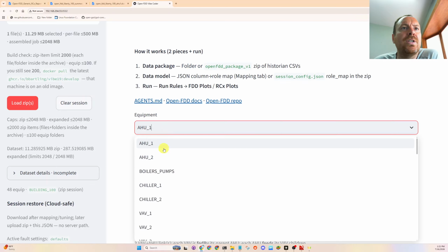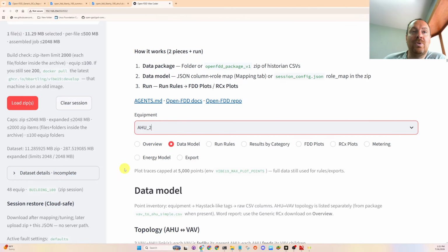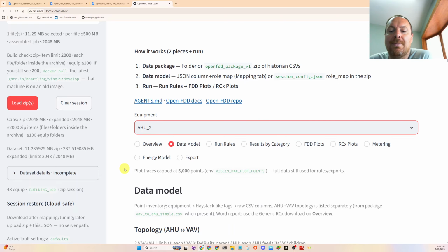And then I also have to change this to air handling unit 2. And then we can go rerun all of our faults. Before this video gets too daunting, I just want to study those economizer faults, and then maybe zero in a little bit on this air handling unit 2, with the sensor reading about 5 times higher than what it should be in static pressure. Zero in on that part too.